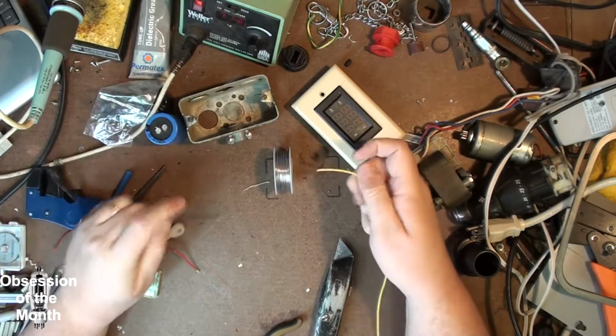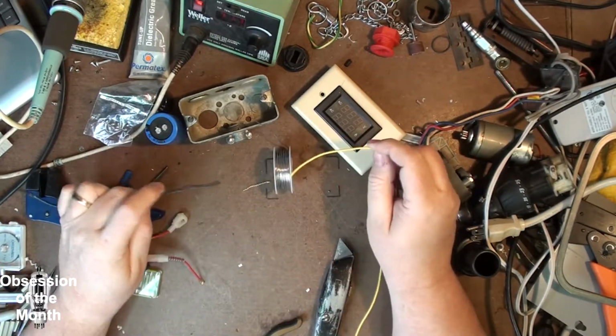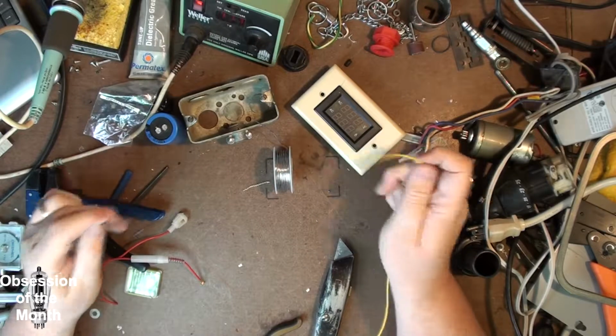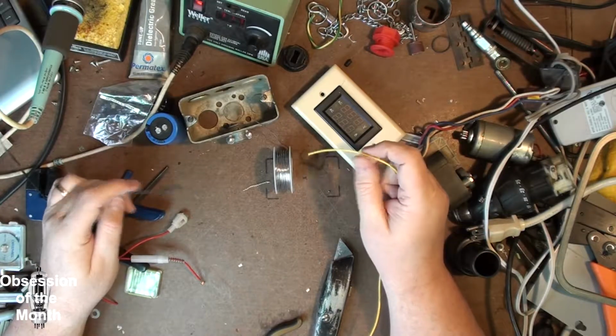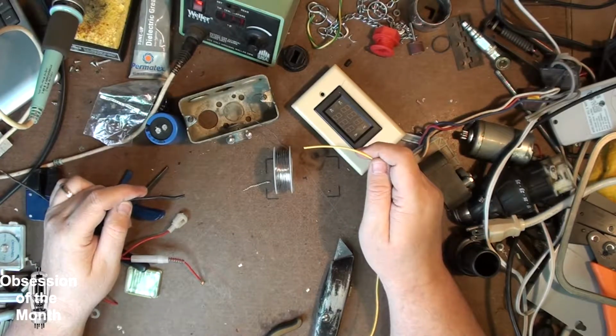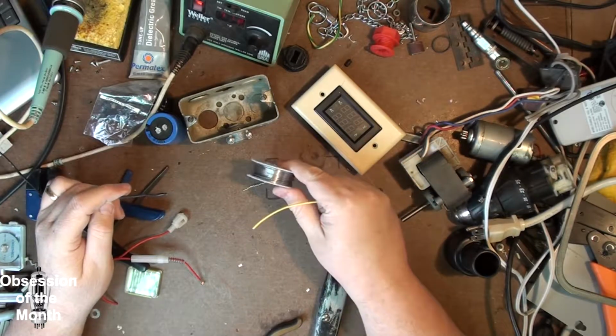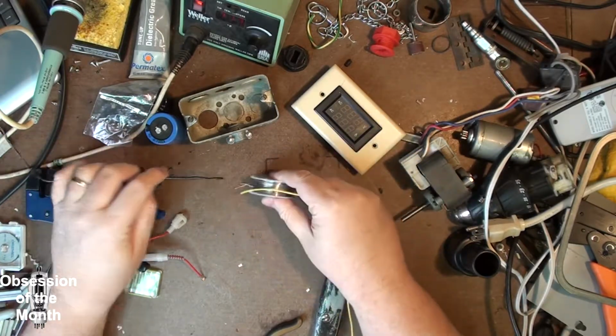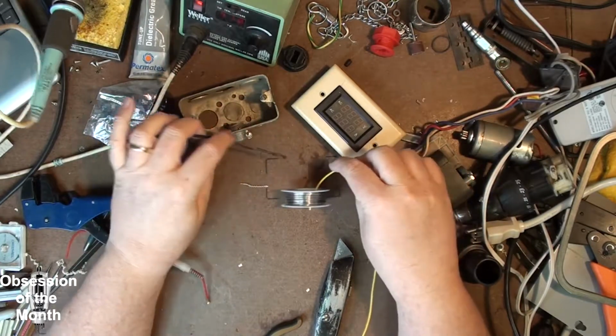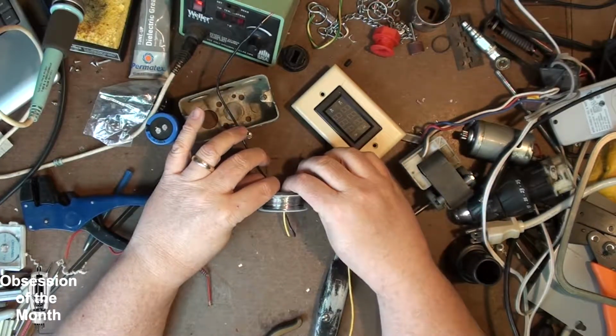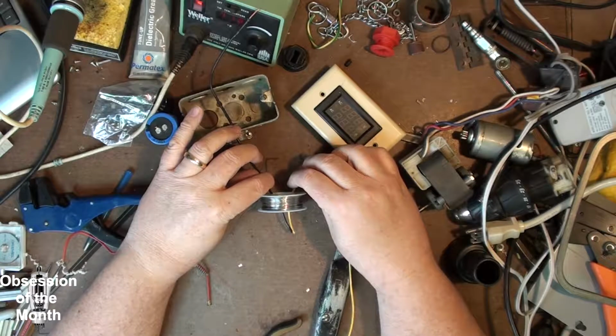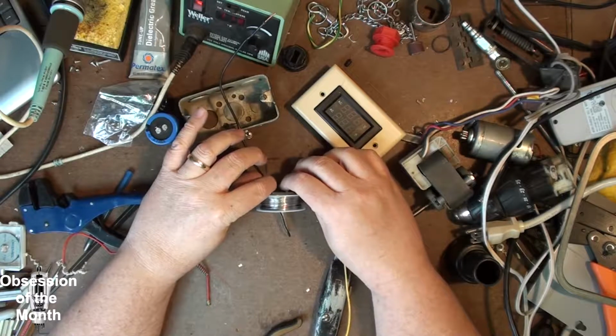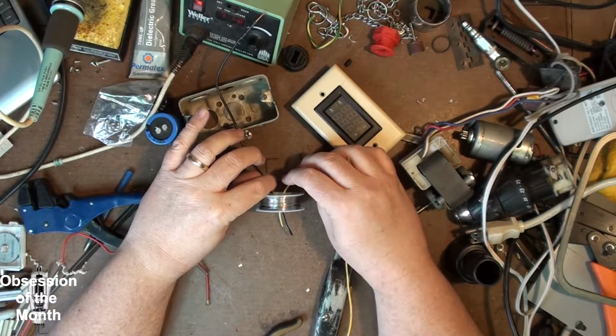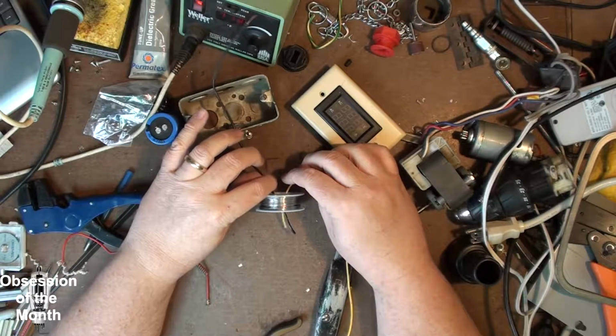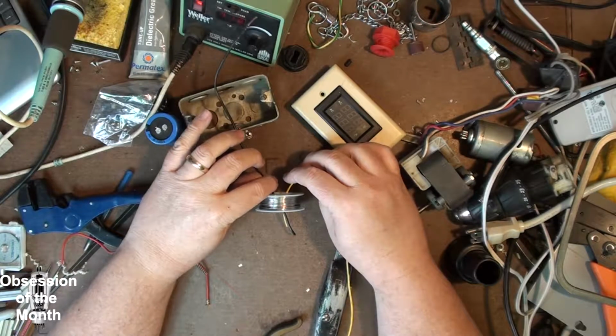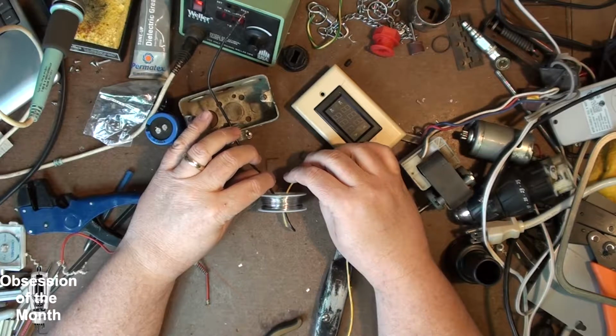Normally you have 2 wires coming in and a neutral. I'm not going to worry about the neutral because you don't ever measure your amperage off the neutral. If you take this and run both wires through here, even though they're both 120 volts with different loads, you will get a reading of 0, because everything is split phase and the loads are 180 degrees out of phase.